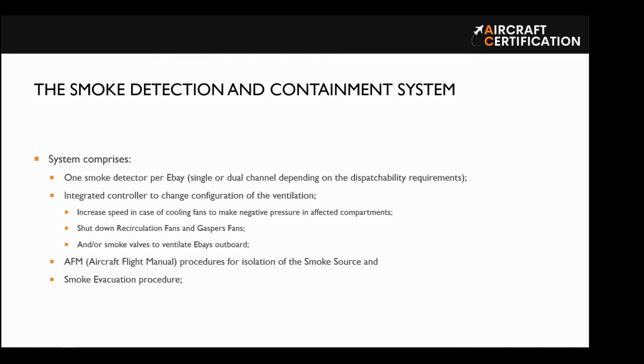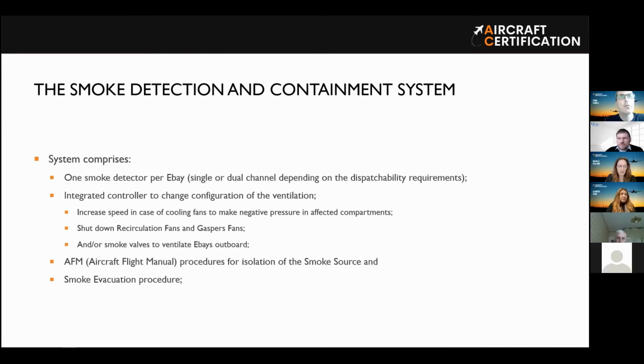The system will shut down the recirculation fan, and it will also speed up the bay fans, because given that we have smoke inside the bay, we need to create a negative pressure inside the bay to avoid the smoke ingressing back through the air conditioning return area, okay?